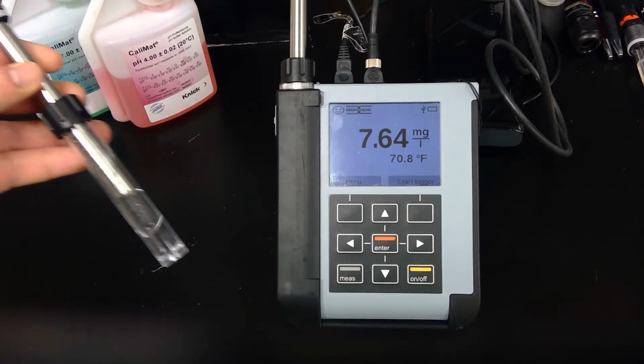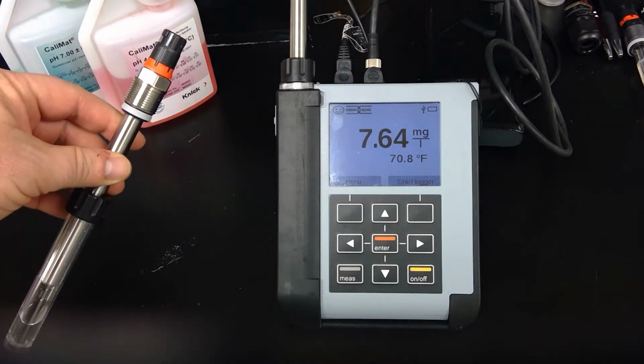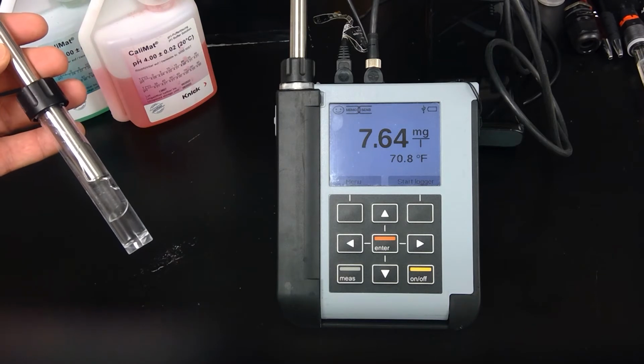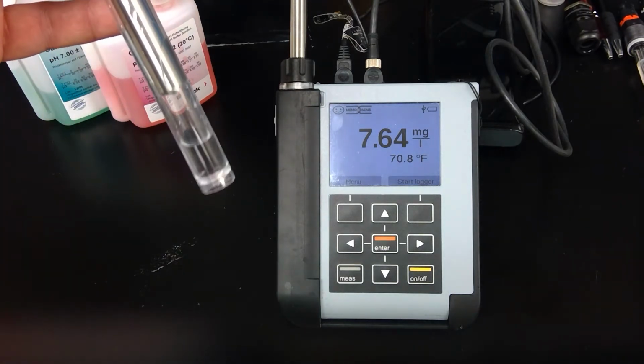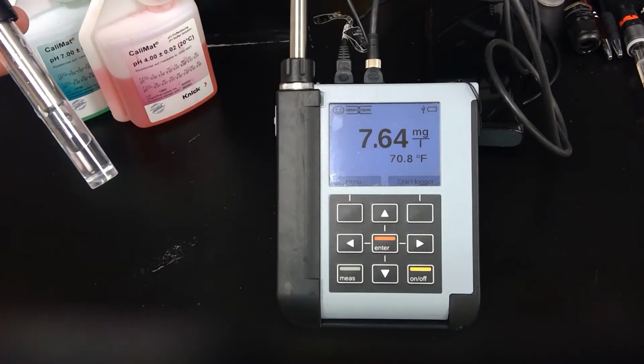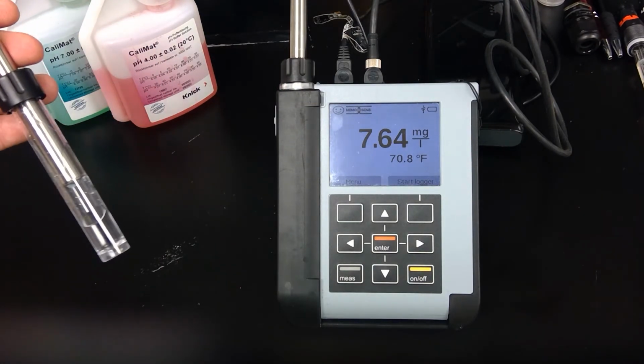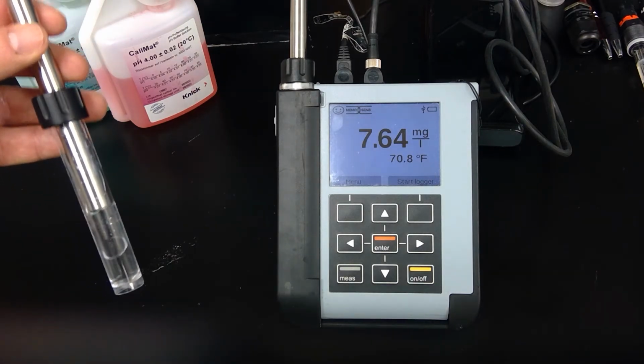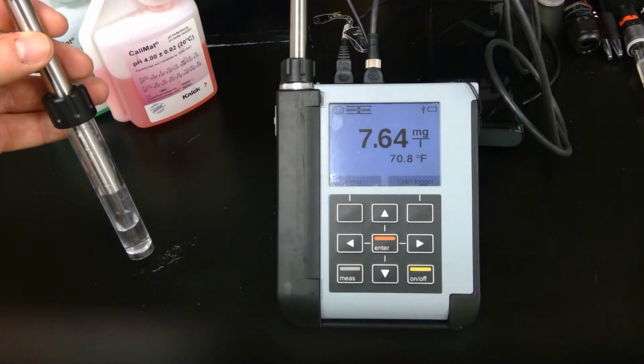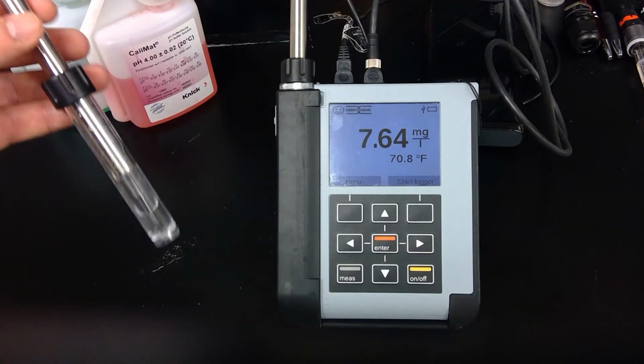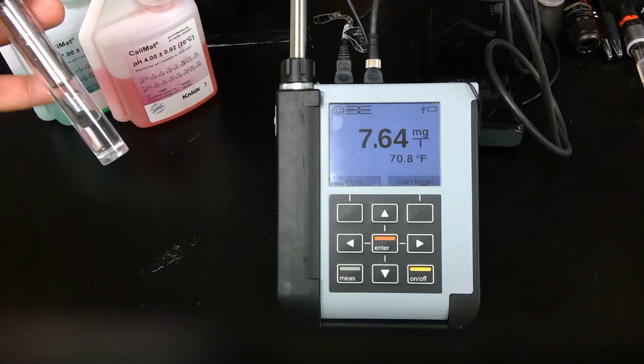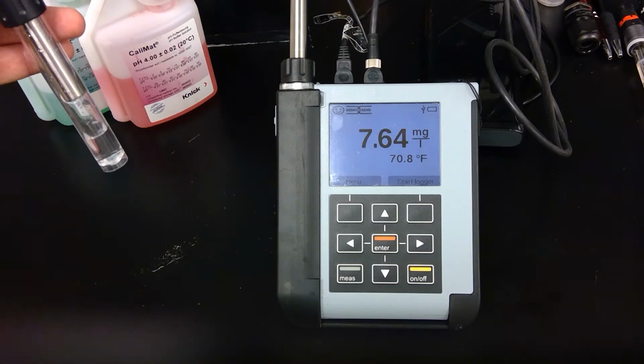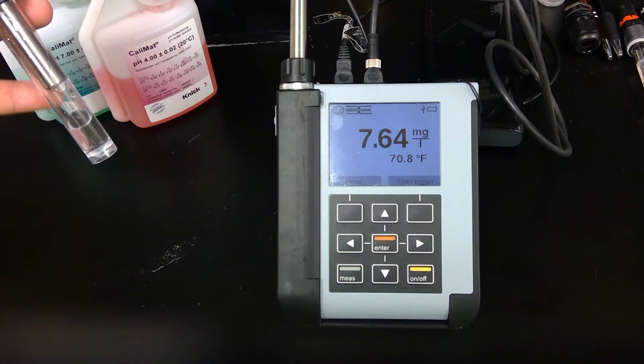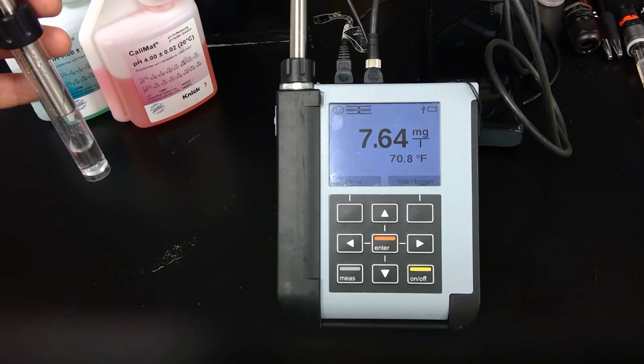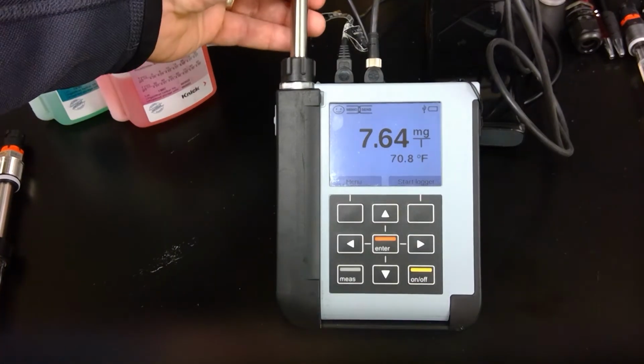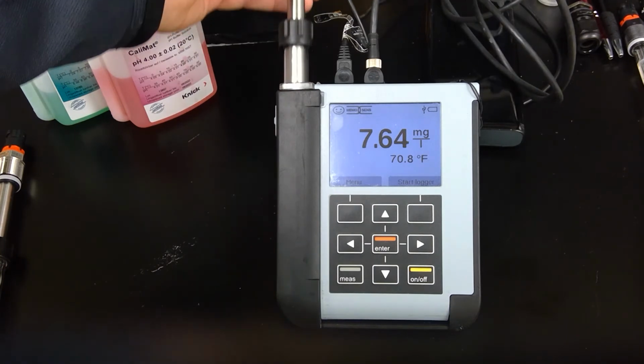So just to point out, this is again an SE706 and it's already inserted into the calibration beaker, and if you look closely you'll see there's a little bit of tap water in the bottom. Whenever we do a basic calibration for an application where it's ambient pressure, an immersion style installation or an ambient pressure pipe, we want to do a 100% humidity calibration. So by putting a little bit of water in there and leaving the sensor for 15-30 minutes, that'll be a 100% relative humidity environment. So I've already got one set up here on the Portavo.